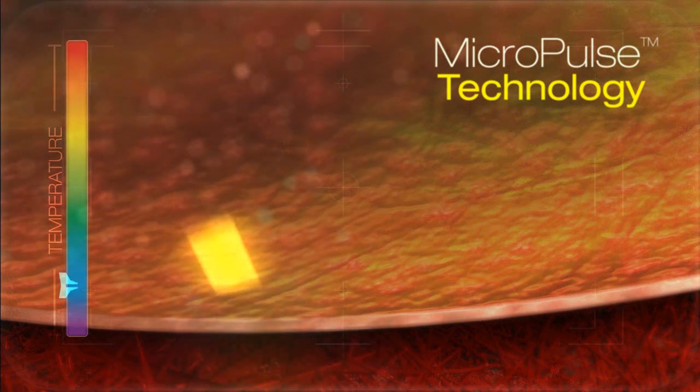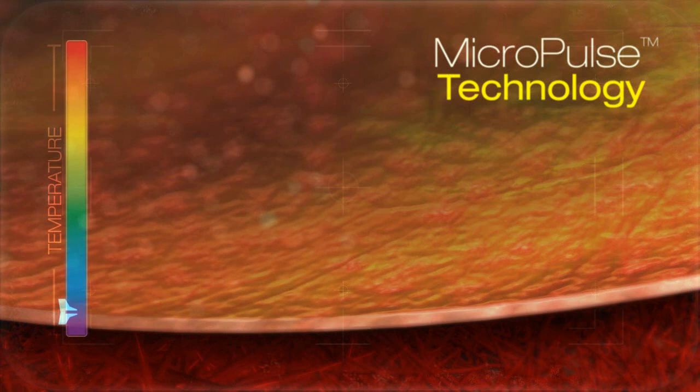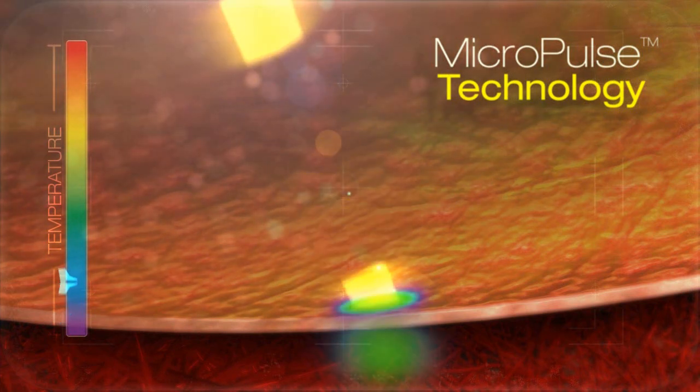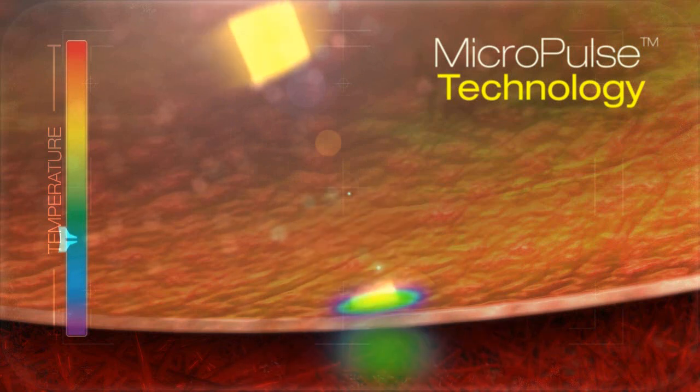Shorter pulse times limit the laser energy being applied, lowering the spread of thermal energy. The following off time allows tissue to start a return to baseline temperatures prior to the next micropulse.